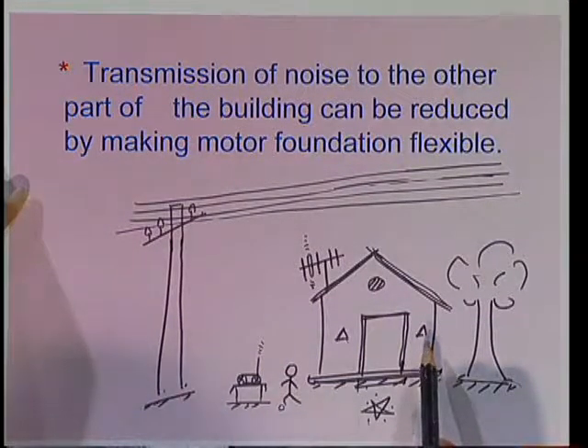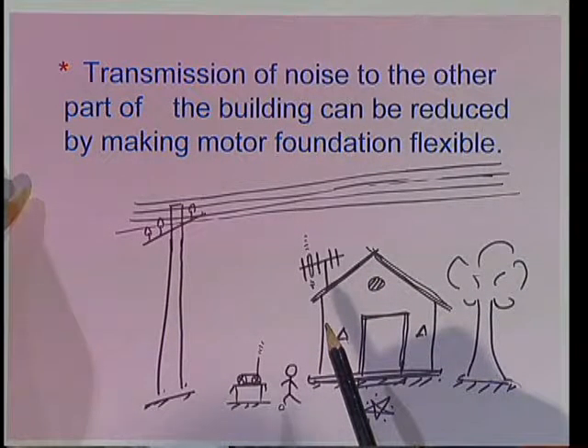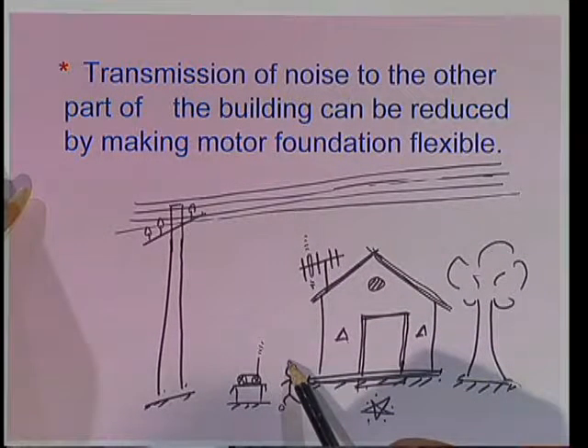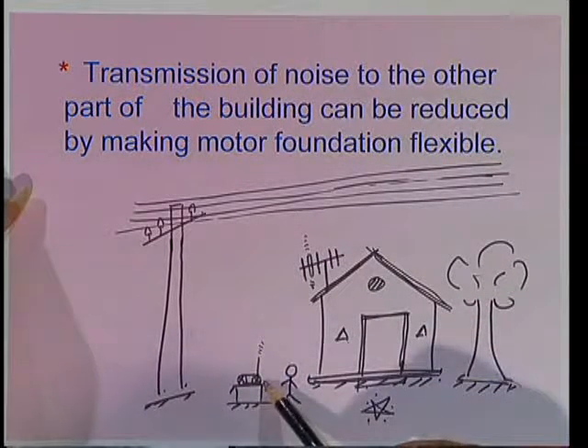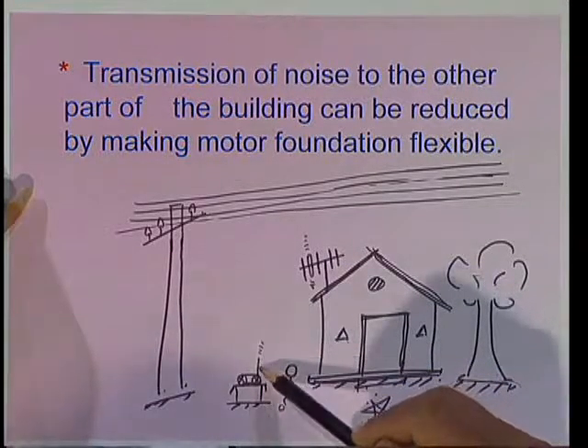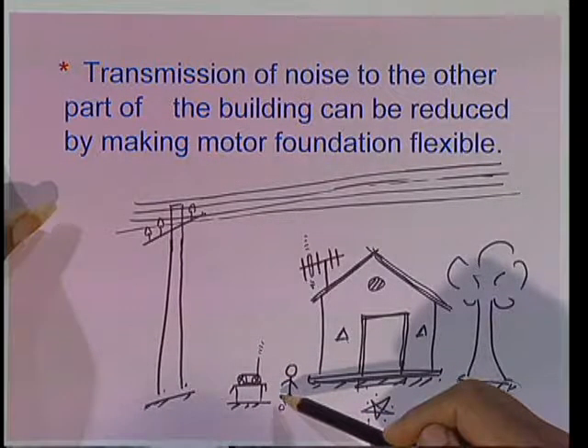There is another type of noise. In domestic applications, if you are using a mixer or other commutator motors while running the TV or radio, there may be some noise in the TV or radio. This is because the supply lines cross over the aerials of the TV or radio, inducing some EMF in the aerials, which gives noise. Generally, this type of noise can be reduced by connecting a capacitor across the motor.